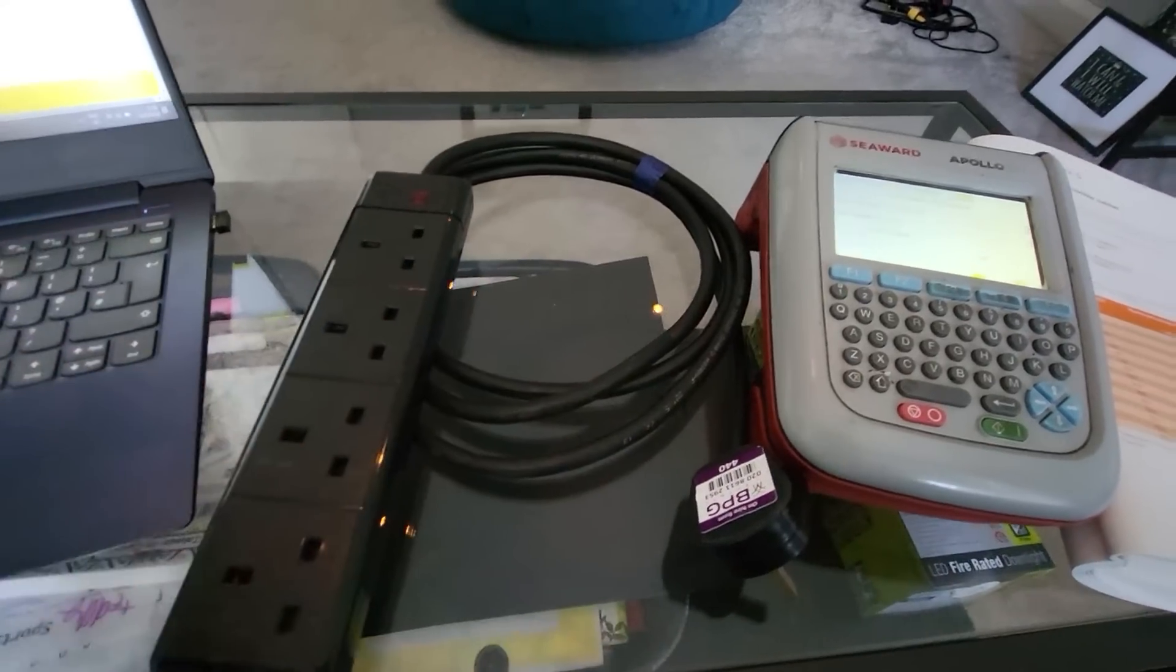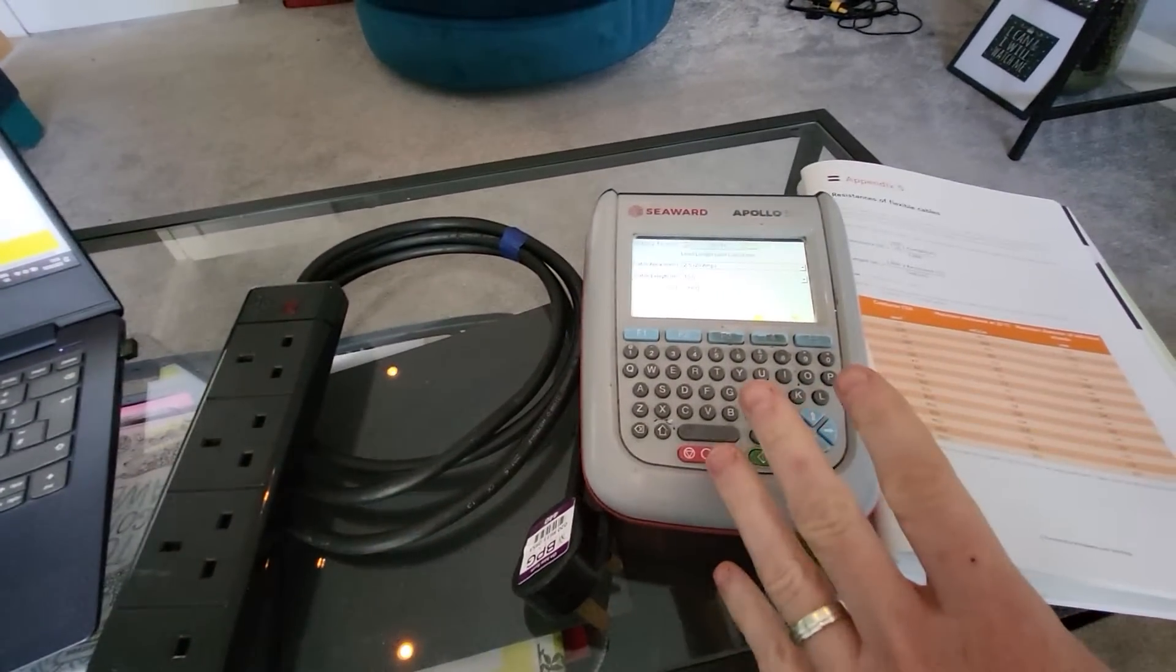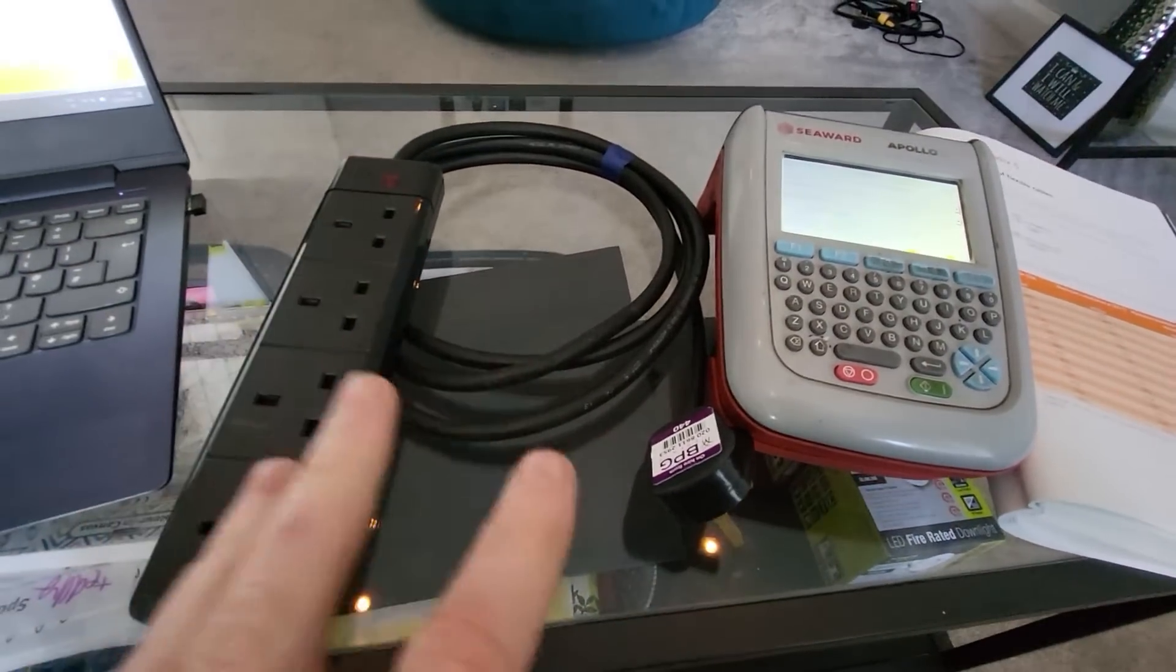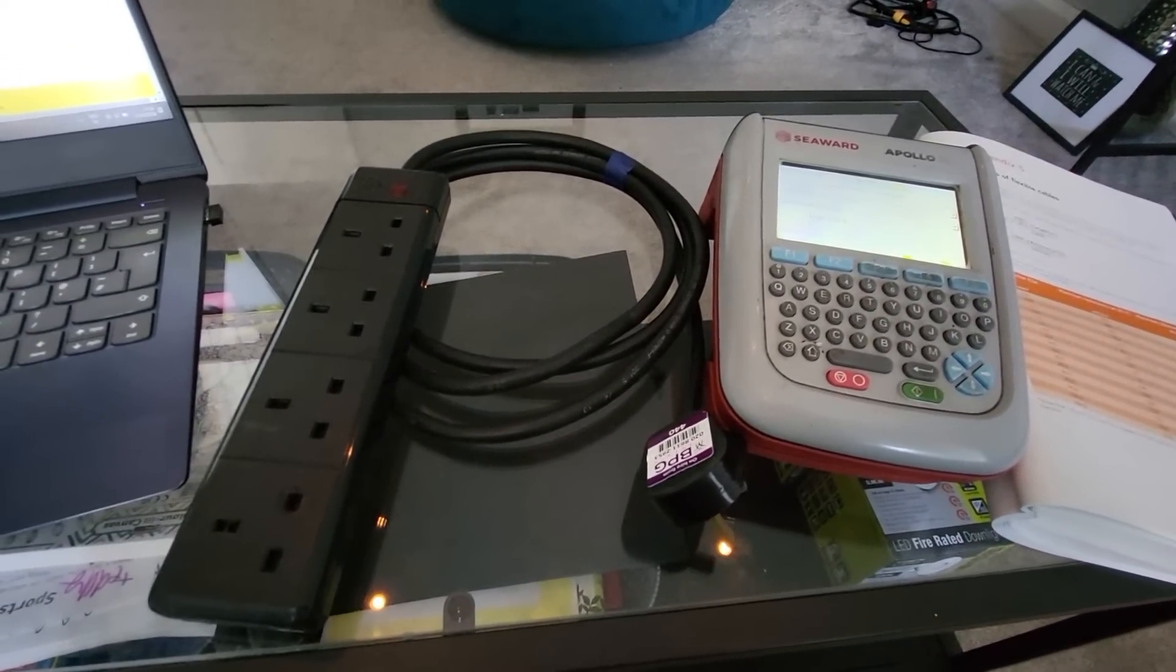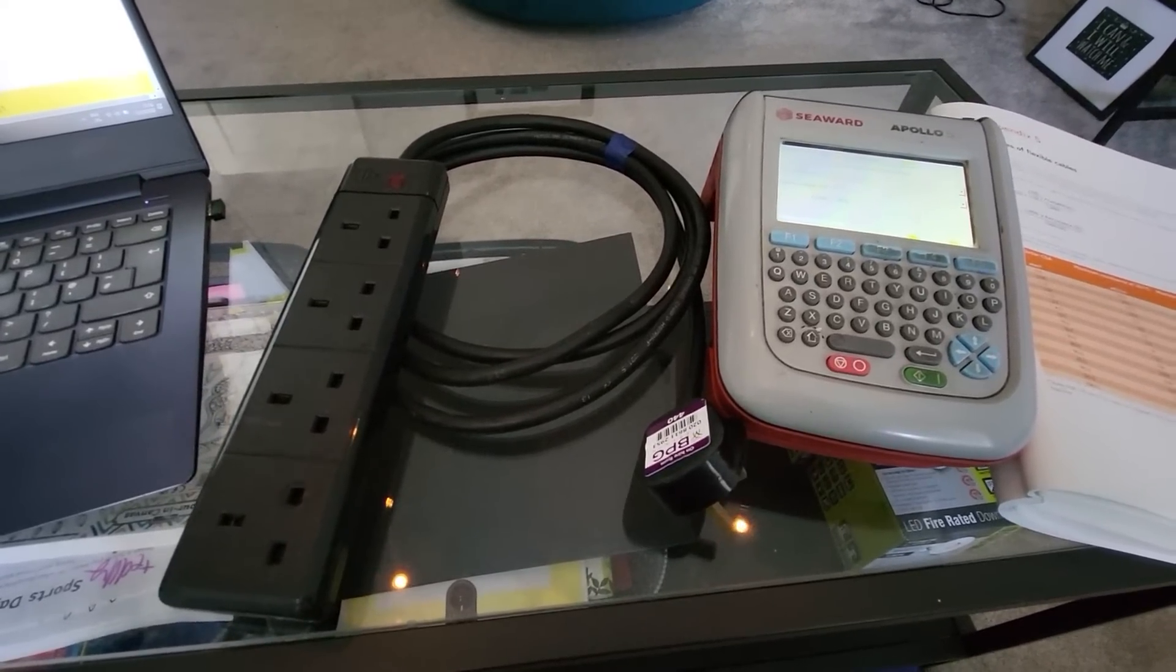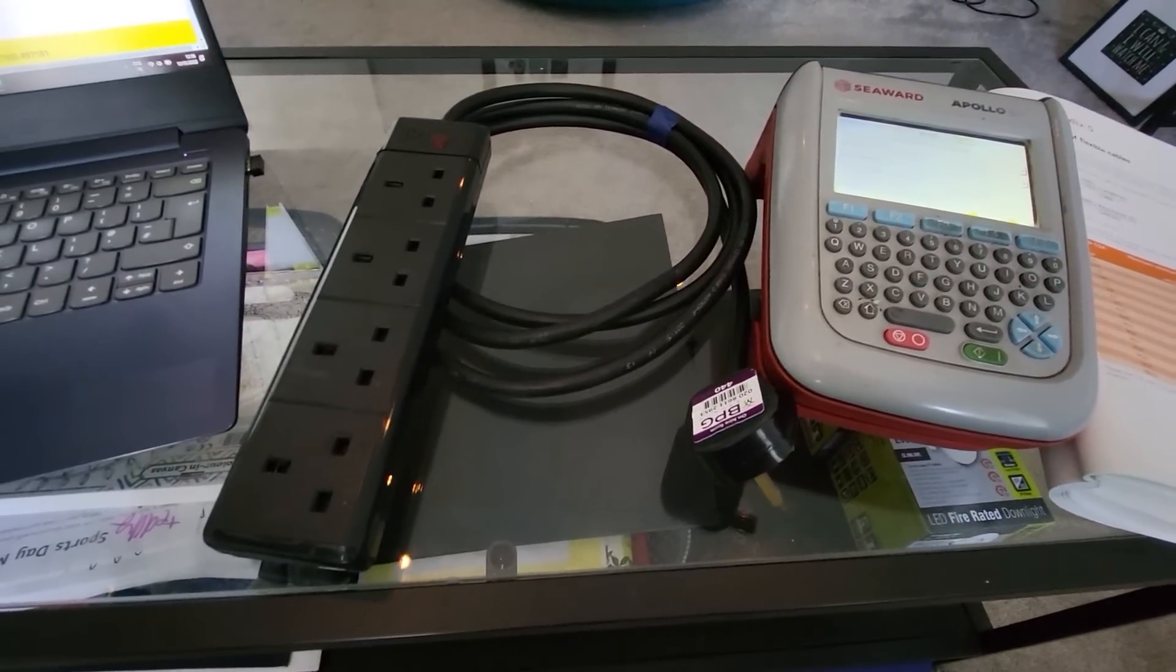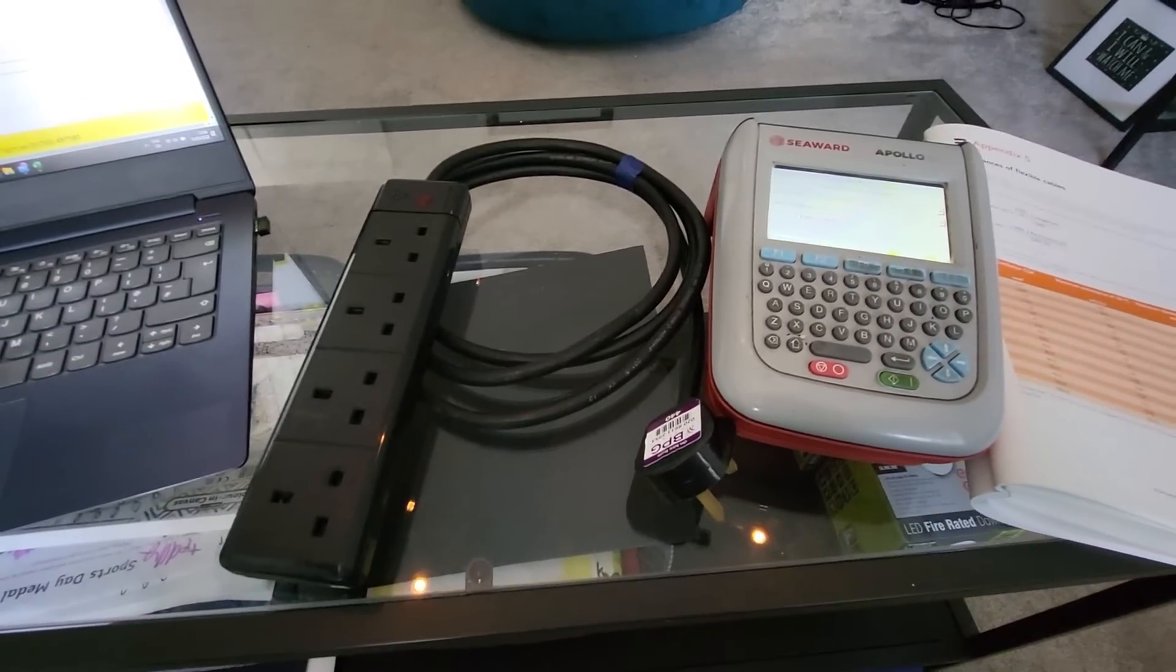So when you're PAT testing an extension lead through your machine, now I'm lucky enough to have an Apollo here, a 500, as you see. Obviously when you're testing different length extension leads, the reading you will get on the Earth Continuity Test will change depending on the length of the extension cable. So if it's from a 2 metre and you were testing a 25 metre, that Earth reading would vary.